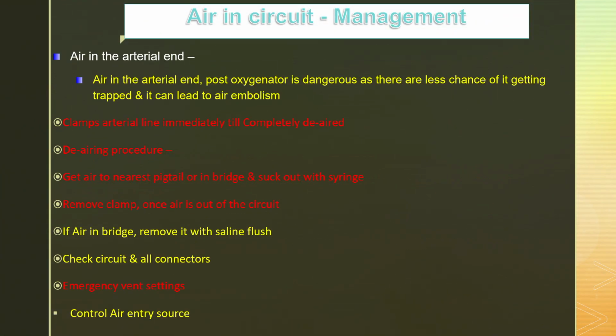From the arterial end, as I told you, if there's air, it's going to be difficult. First of all, put a clamp, and if you see the air is there and you have a bridge, take the air into the bridge. You can close the bridge and start circulation immediately, so you will not waste much time, if it is in the bridge.